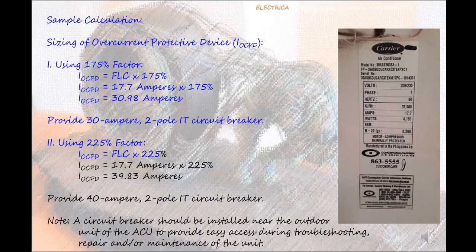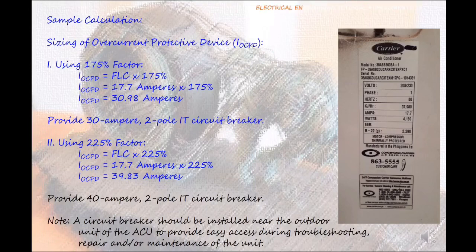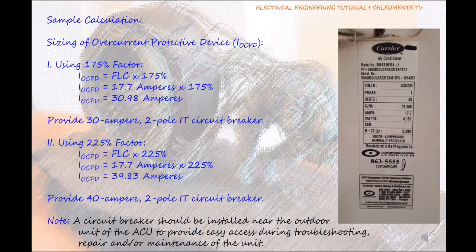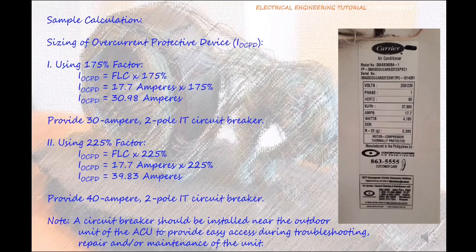If the 175% factor will not be able to carry the compressor motor starting current, IOCPD equals FLC multiply to 225%. IOCPD equals 17.7 amperes multiply to 225%. IOCPD equals 39.83 amperes. Provide 40 amperes, 2 pole inverse time circuit breaker. Note: A circuit breaker should be installed near the outdoor unit of the ACU to provide easy access during troubleshooting, repair and or maintenance of the unit. In this circuit, we will provide two 40 ampere circuit breakers, one near the outdoor unit and the other one in the main distribution panel.